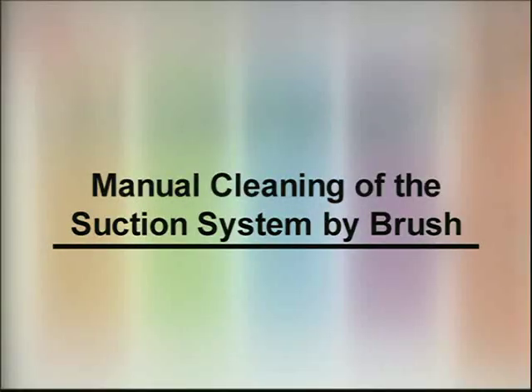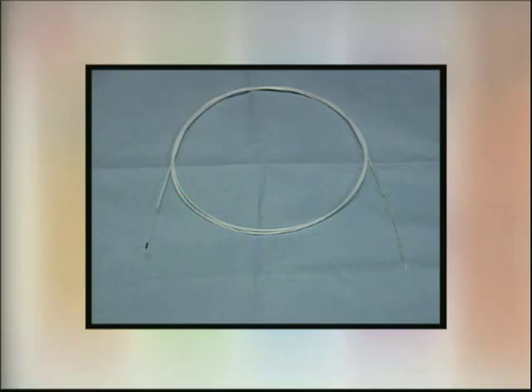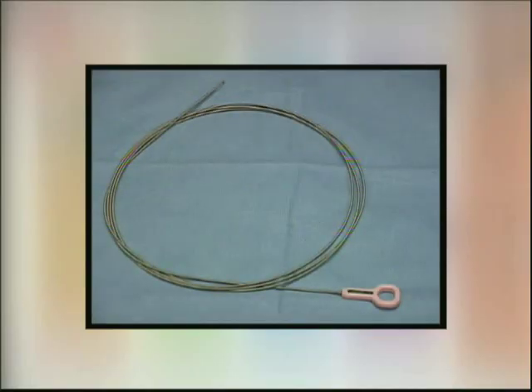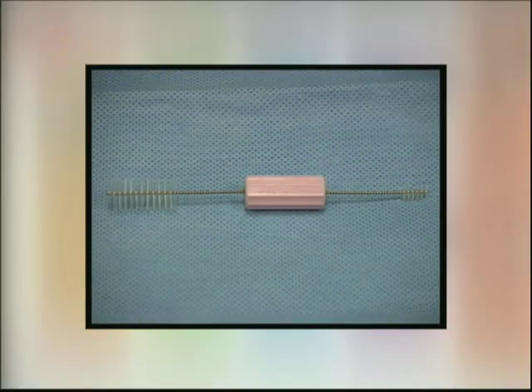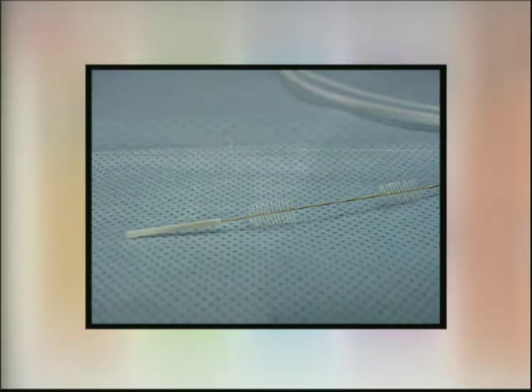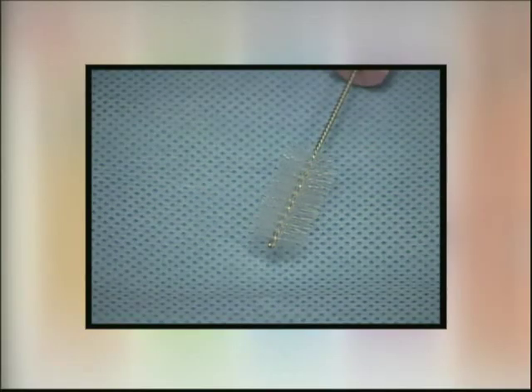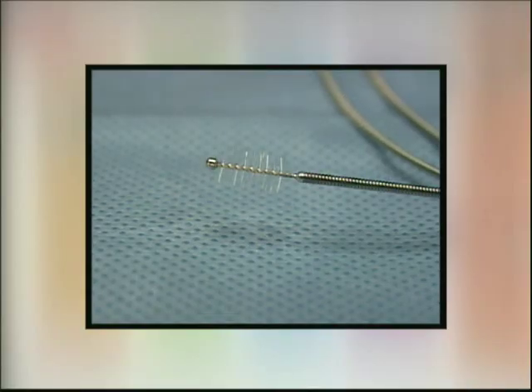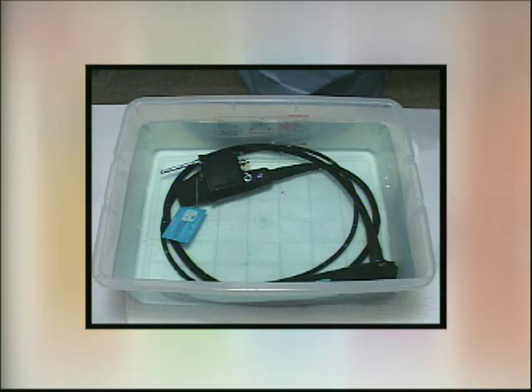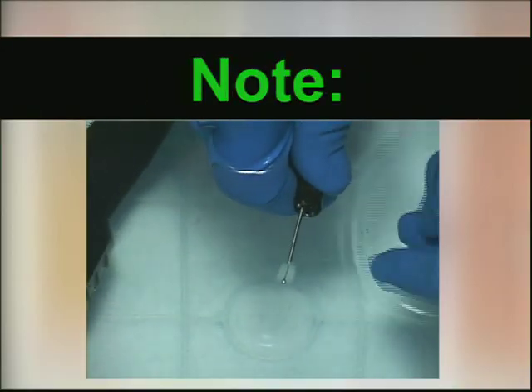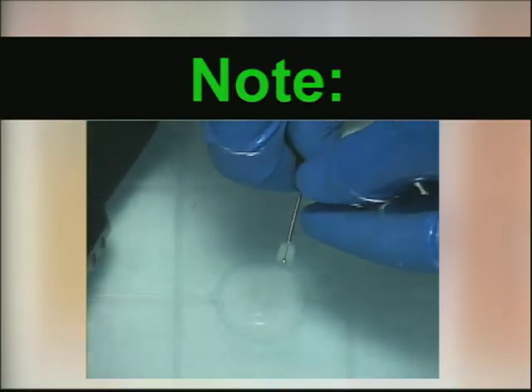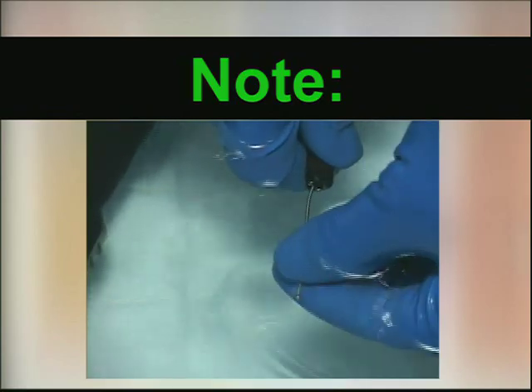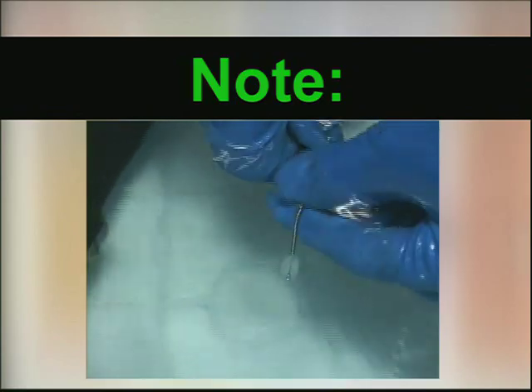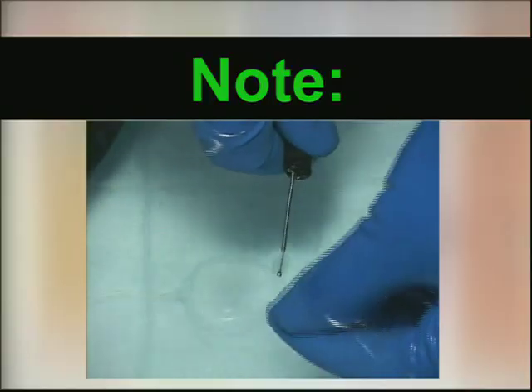Manual cleaning of the suction system by brush. A variety of special brushes have been provided to mechanically brush clean the entire suction instrument channel. Reusable brushes should be examined before use and should only be used if they are in good condition. Whenever possible, the entire endoscope should be immersed in detergent solution during the remaining of the cleaning procedure. Note: prior to inserting a used cleaning brush into any channel or opening, always clean off the bristles to avoid reintroduction of patient material and/or contaminants back into the scope.